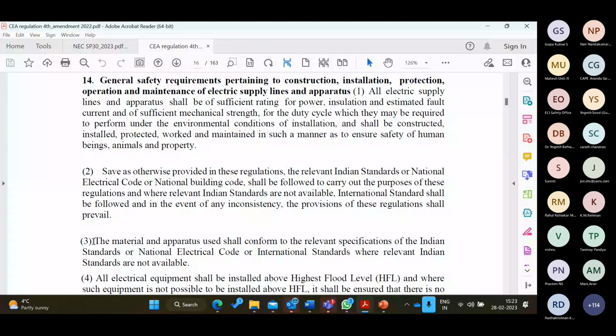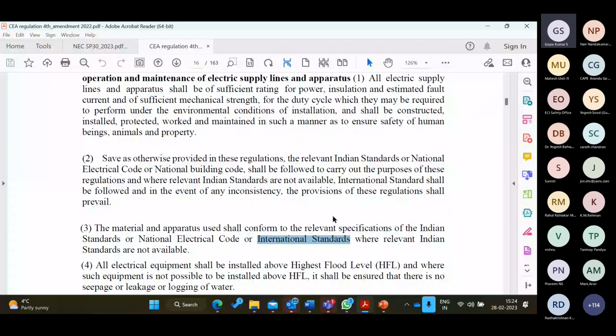Number 3, material and apparatus used. Materials and apparatus used shall conform to the relevant specification of the Indian Standard or National Electrical Code or international standard where relevant Indian Standards are not available. So this also means, as I said, there is a definition for international standard. International is not like Pakistan or Bangladesh standards. This is IEC, ITU, or ISO standards. So basically, the products used in an electrical installation shall be as per the Indian Standard. So basically, these two regulations have changed the situation.